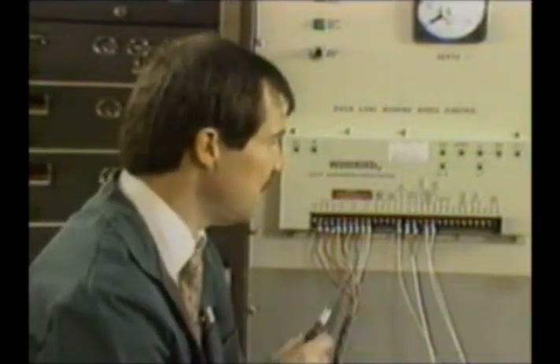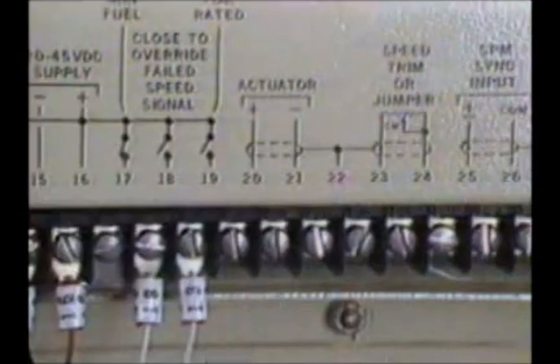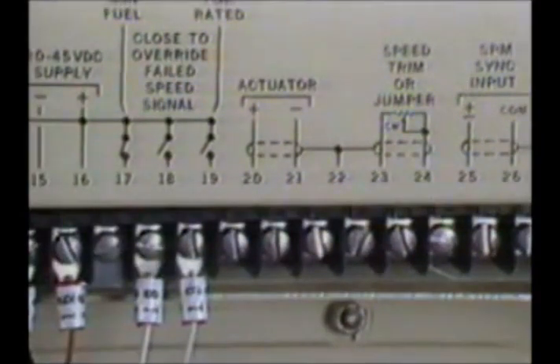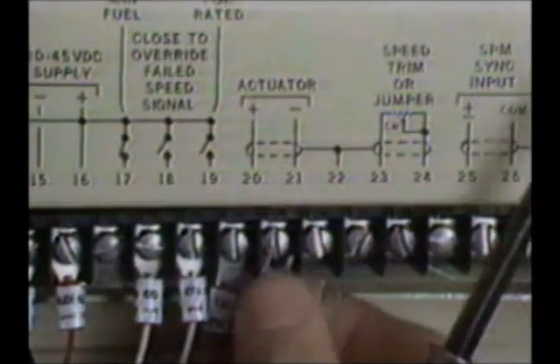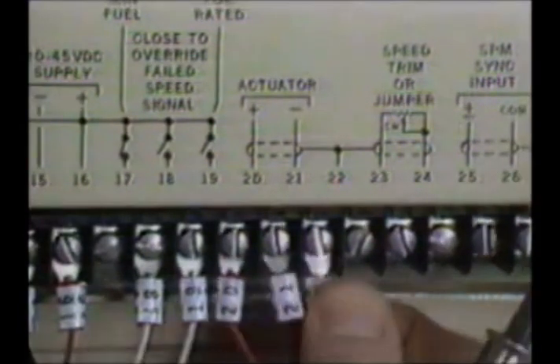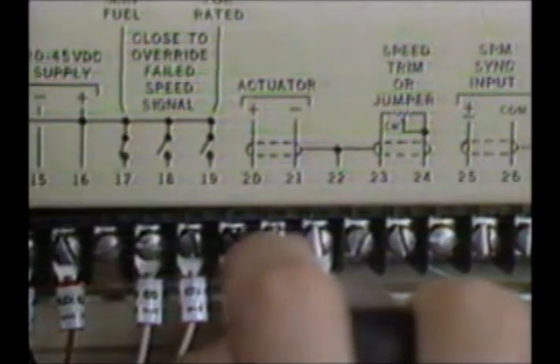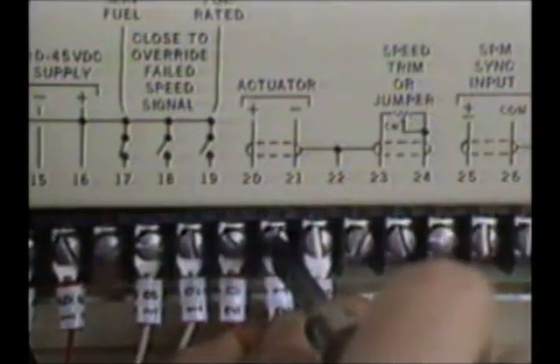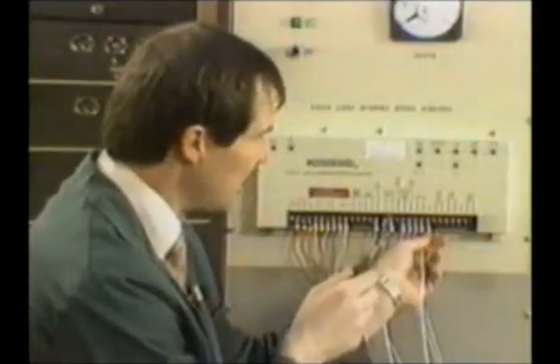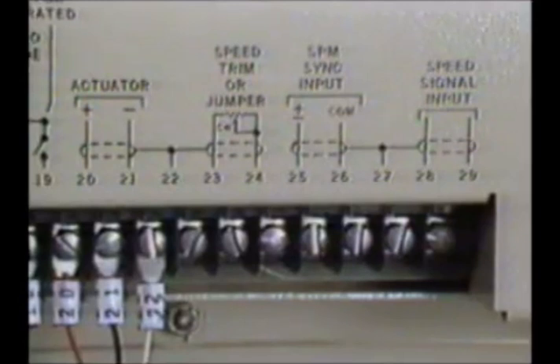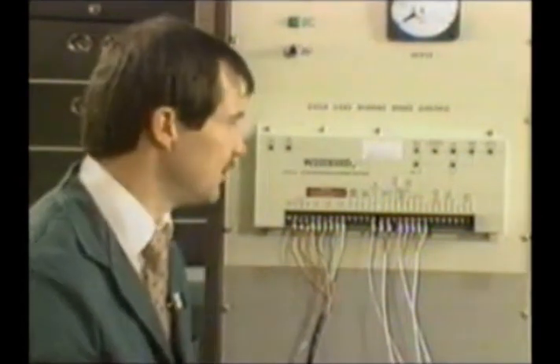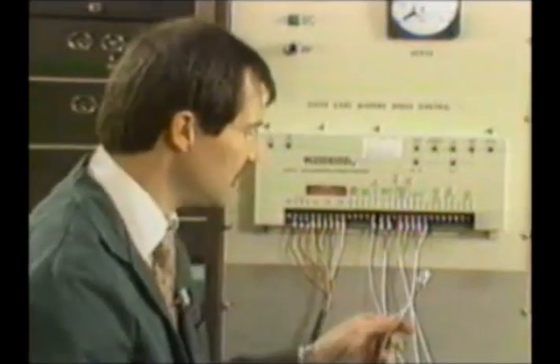Now we're up to terminal 20, and 21 is our actuator input, with 20 being positive. Now you can see that's a shielded pair with 22 being the shield for that. So I want to make sure I terminate the shield for my actuator at the control here. So let me hook up. And 22, and before I hook 22 down, my next ones, 23 and 24, are for speed trim or a jumper, or it can be a digital reference input. But that shield also goes to terminal 22, so I'll have two shields on terminal 22.